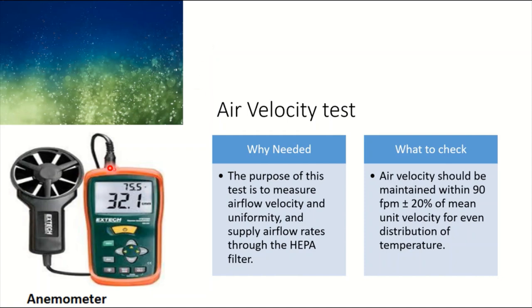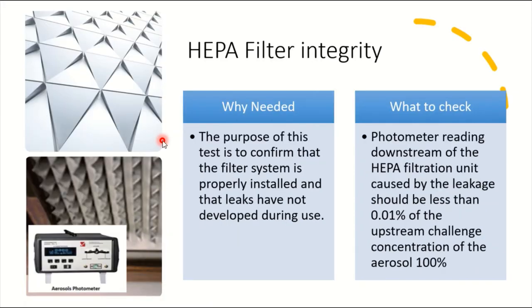Our first study is air velocity test. This is very familiar equipment—we have seen this machine in HVAC system validations. This is an anemometer. The purpose of this test is to measure the air velocity. We have a HEPA and we are expecting certain velocity. The limit is, as usual, 90 feet per minute plus or minus 20%.